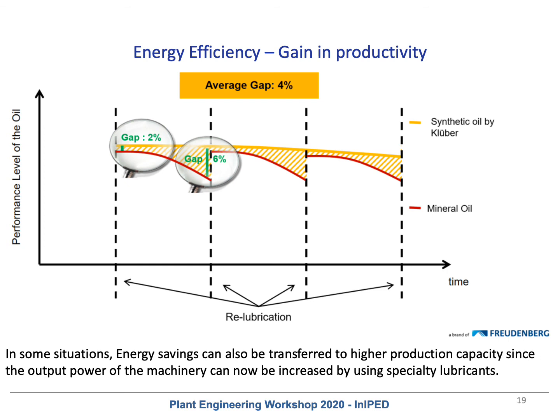This graph explains that by using a Kluber synthetic oil that does not use any viscosity improver like PIB, the gap is right from the beginning around 2% between the performance of a Kluber synthetic oil versus a mineral oil. But as you can see, the normal service life of a Kluber product will be on average 3 times the service life of a mineral oil. So by the time you do 3 changes, you only do 1 change with the Kluber synthetic oil.